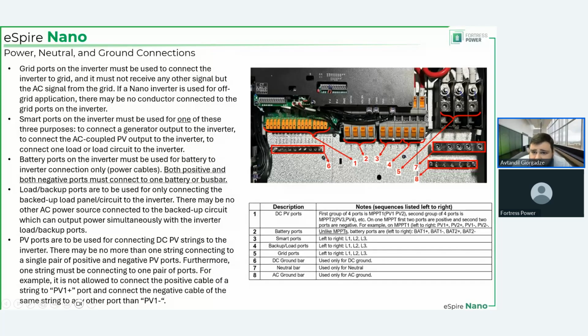Then you have smart ports. You have L1, L2, and L3. These smart ports are used for either generator, AC coupled PV, or smart load. Now, it's not like either or, well, once the system is commissioned. Whatever you commission the system with and whatever you configure these ports for, that's how it's going to be, unless you completely change your system layout, and instead of the AC coupled PV, you decide to remove that AC coupled PV altogether and put in the generator, right?